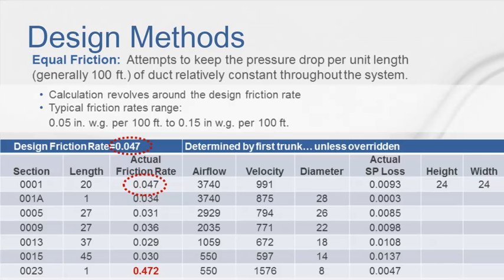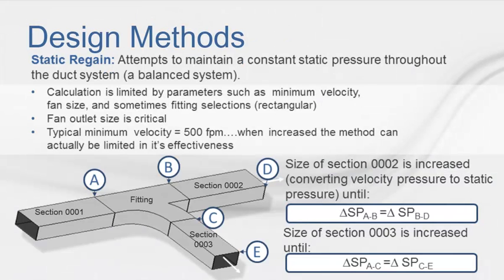Duct Designer supports both the equal friction and static regain methods of duct design. If you've been using the ductulator to design your duct runs you're already familiar with the equal friction method, which attempts to keep the pressure drop per unit of duct length relatively constant throughout the system. In contrast, the static regain method attempts to maintain a constant static pressure throughout the duct system. Due to the calculations required, the static regain design method is impractical for hand calculations; however, it's the ideal method when designing a duct network on a computer.